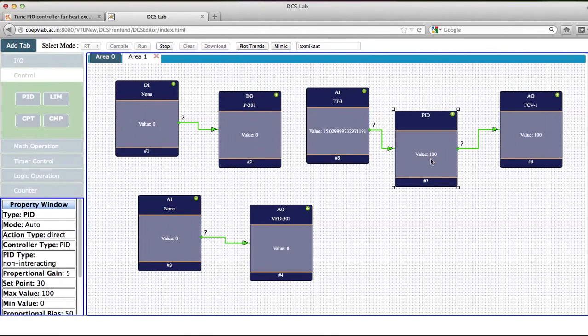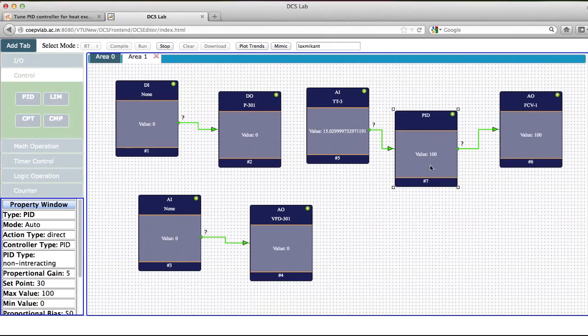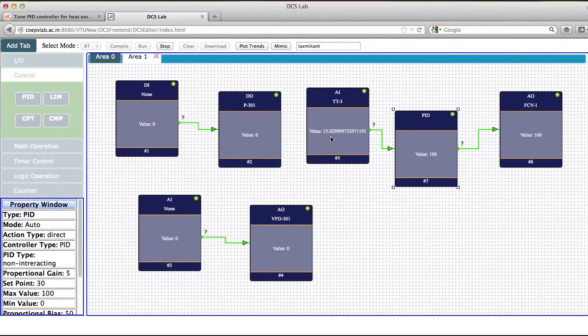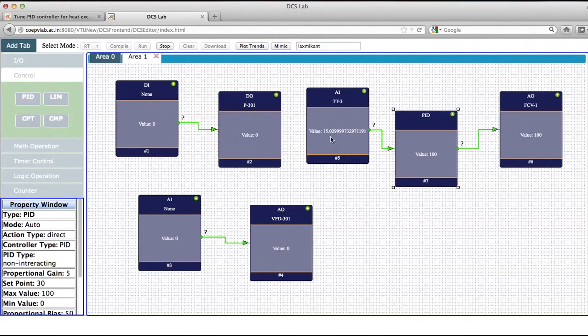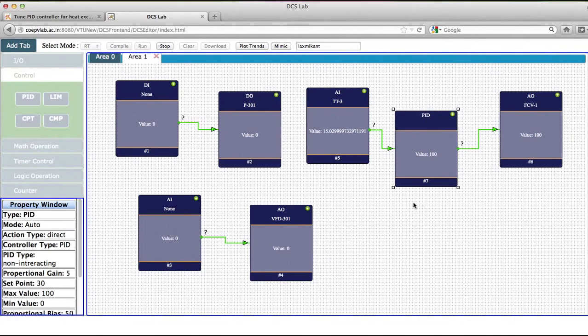Then you will find that the values will start coming up. The PID is now 100 because this set point is 30 and the temperature at present is 15. That means there is a gap of 15 percent. So the valve has fully opened.